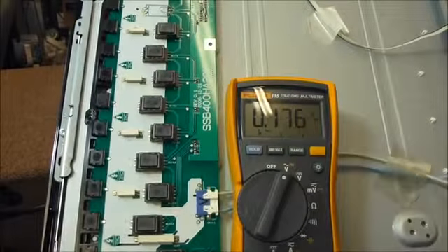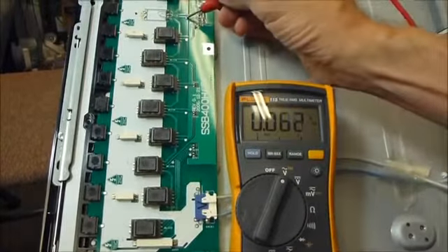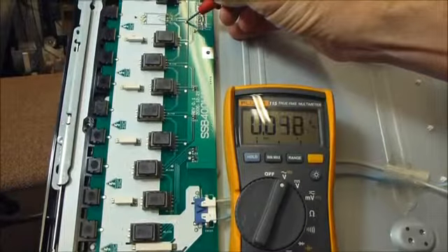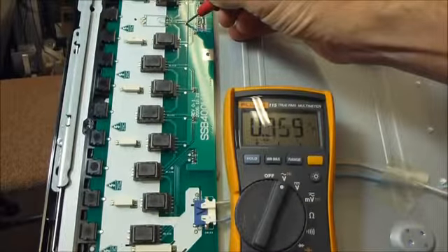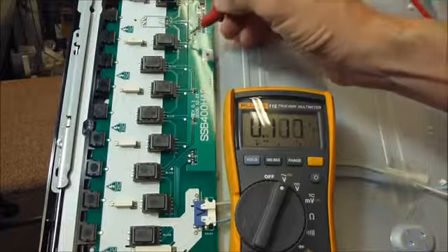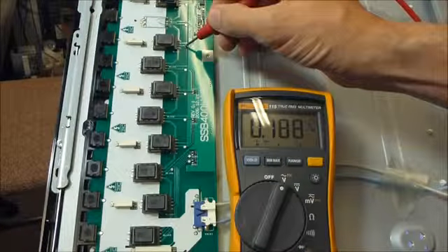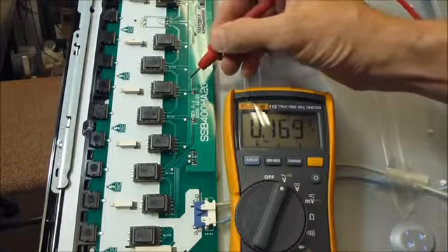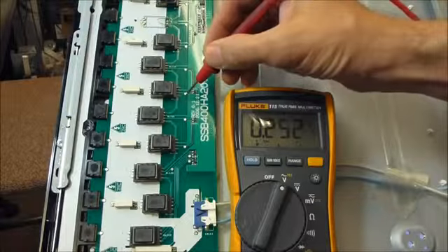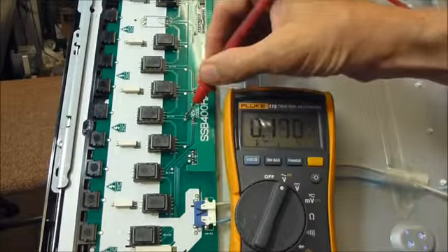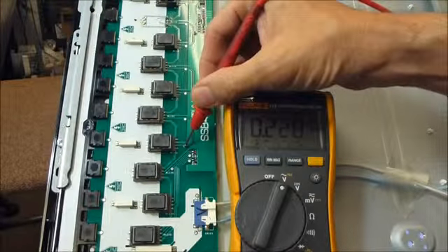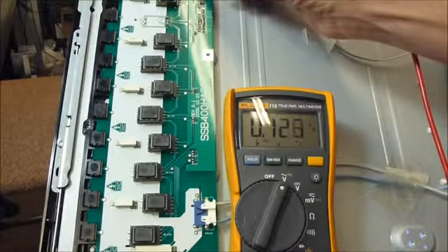Now there's nothing connected to this feedback line, so it's just going to kind of float around and do whatever. You can see it's 1/10 of a volt. The other ones are 1/10, 1/10, 2/10. That one's drawn a little bit more. It's when it gets up into the like 3 volt range that it causes the set to shut down.